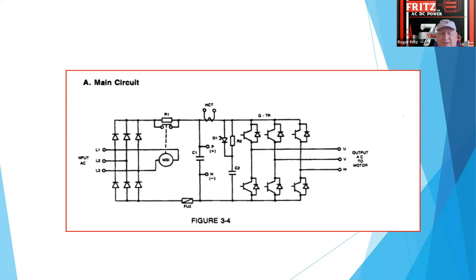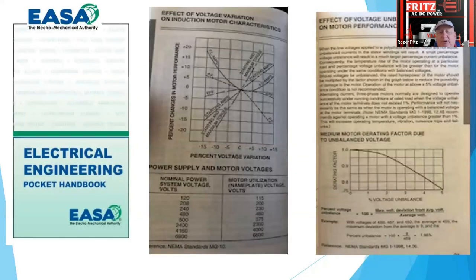This happens to be another circuit, a little bit more detailed as to what they're doing. This has the diode front end. They added resistors in here to slow down the current. Then they have a contactor, and after the capacitor gets charged, it shorts that out, so this is a shorting circuit. They have some Hall CTs in here to monitor the currents. Then they have some diodes feeding the capacitors, and again capacitors here. It's all just to get this DC power supply up to par before we start turning the transistors on with output.